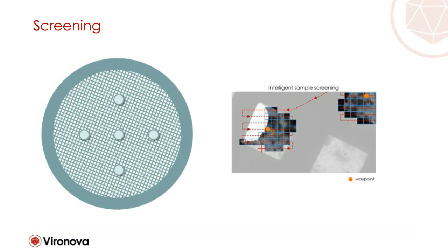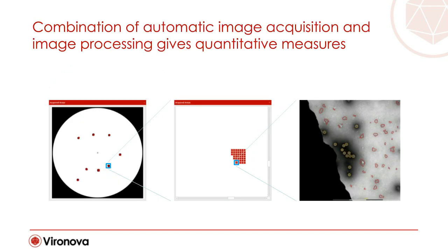Each waypoint will be visited and each area will be imaged in a structured way. This would take a few hours if it's done manually, which for an experienced expert would not be an attractive task. So the system moves from area to area and collects images at each area based on user configuration. Each image is processed and particulate matter such as the primary analytes, but also undefined structures of interest, are registered and accounted for.